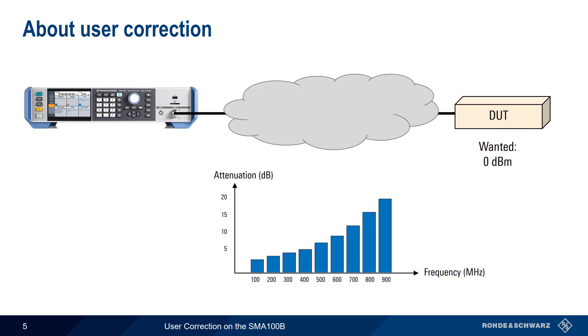User correction is implemented by using a table that maps frequency to a correction value. The generator looks in the table and changes its output power by the amount indicated for the current frequency. This allows the generator to provide a consistent power level to the device under test over a wide frequency range.